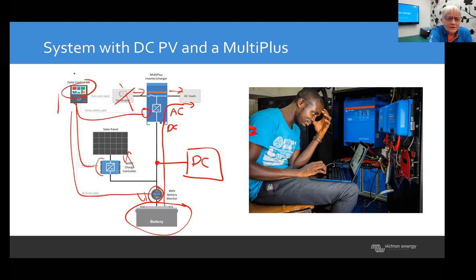Because this system is quite smart, it can also automatically start a generator. So you can say battery is empty, Color Control sees that, starts the generator, and tops the battery up to maybe 80% or so, then waits until the next day to see if the sun comes, and if not, does more. So it can be really, really flexible.